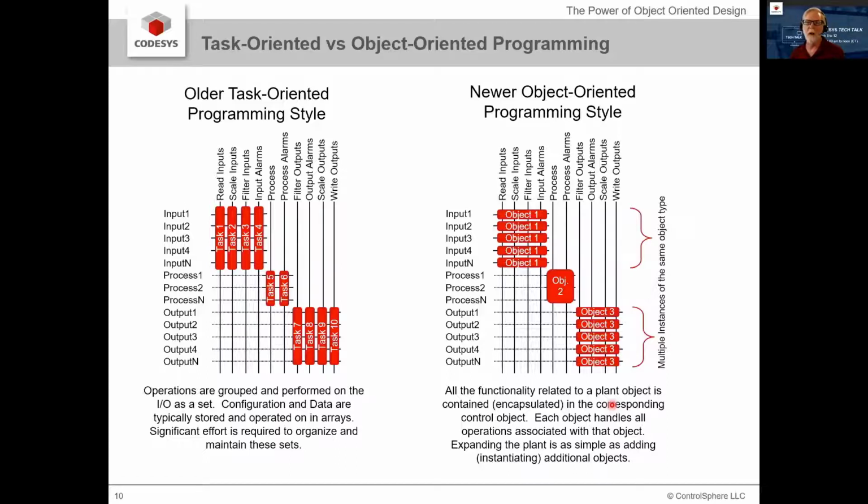For instance, in a task-based approach, the control design is completed first, then the alarm manager is added, and then the persistence manager is added, and then the log manager is added, and then the visualization is added, and so forth and so on. And if you ever have to add something, if you have another input you need to add or some more functionality, you've got to go back and add it to all those lists before you're done. And hopefully you don't forget, because it's a very easy thing to forget.